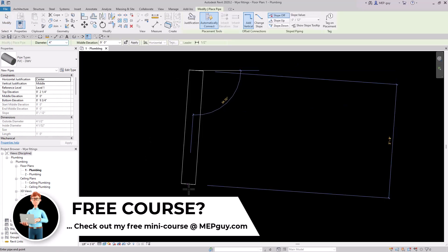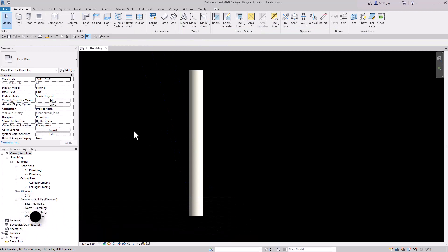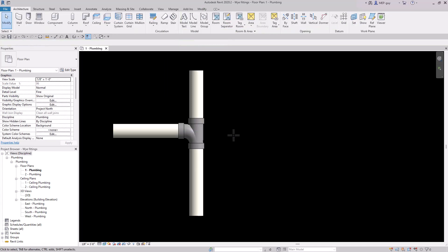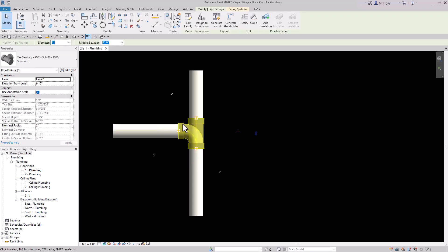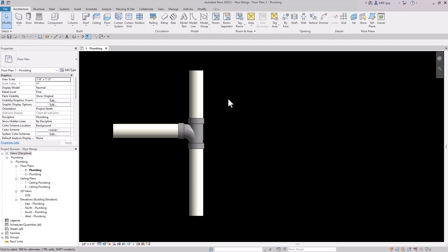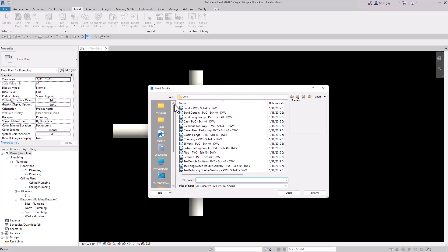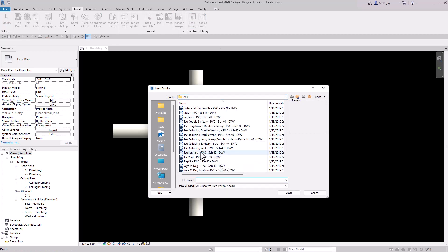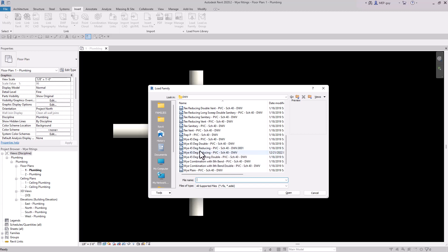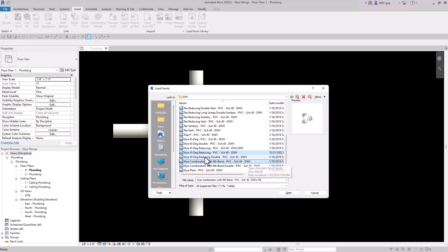I'm going to show you some things I do when modeling. First, we'll go over using a sanitary or combination fitting. I'll draw some pipe and 90 degree into it — Revit creates a sanitary tee at 90 degrees. This fitting is not approved for a lot of situations, so I like to change it to a combination fitting. Let's load one in: go to Insert > Load Family, navigate to the DWV folder, and select the Y 45 degree reducing fitting and the Y combination fitting — the top two sanitary fittings you'll want to use.